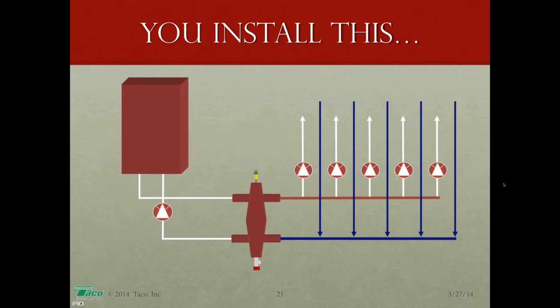In fact, putting a variable speed delta T circulator as your system pump for zone valve distribution is going to help this situation tremendously because since it's varying its speed to maintain that 20-degree delta T, you know you're always going to get a 20-degree delta T coming back, and you'll always have that lowest possible water temperature going back to the boiler. It's going to make it condense even more. So it's not overkill. I think it is an outstanding addition to enhance the efficiency of a boiler that we're already trying to make as efficient as possible. So I hope that answers your question, Thomas. I love questions like that.